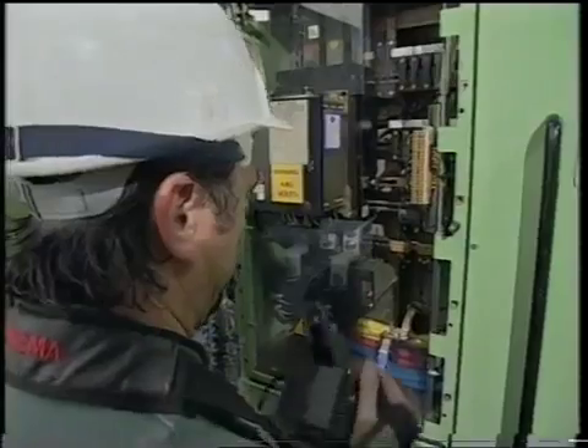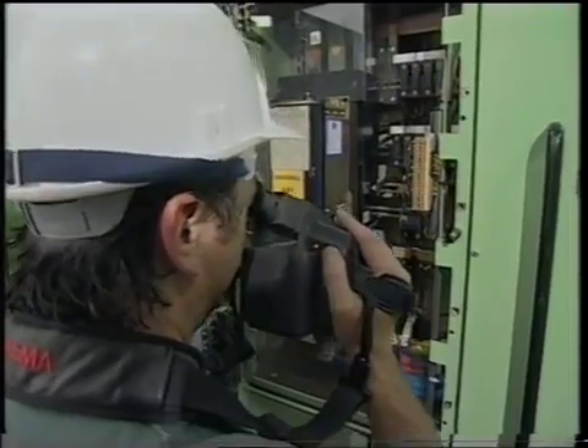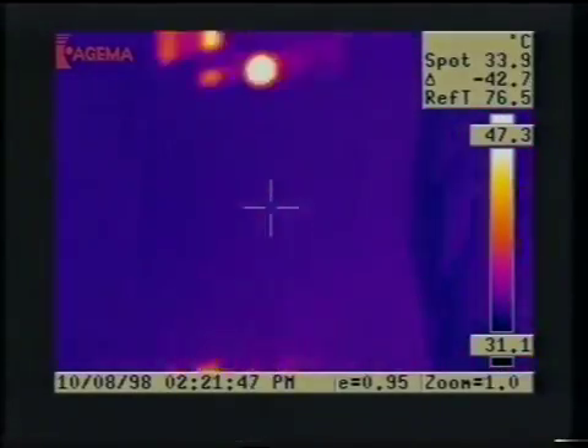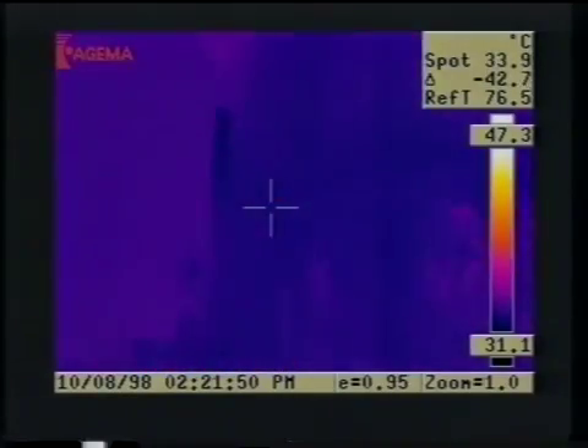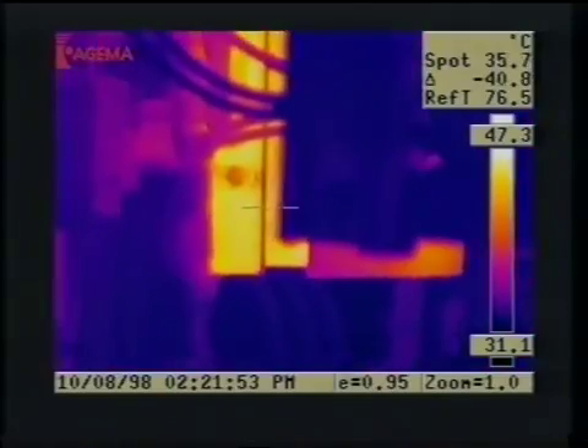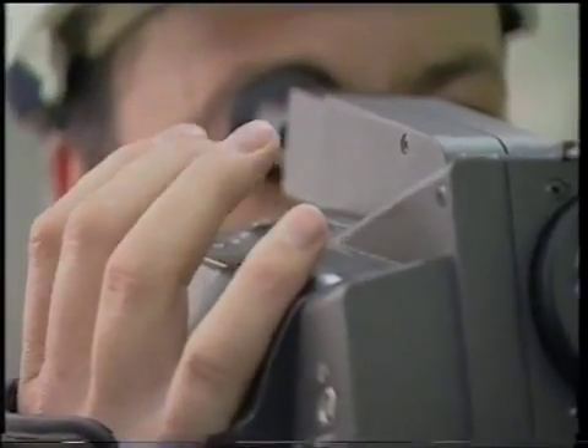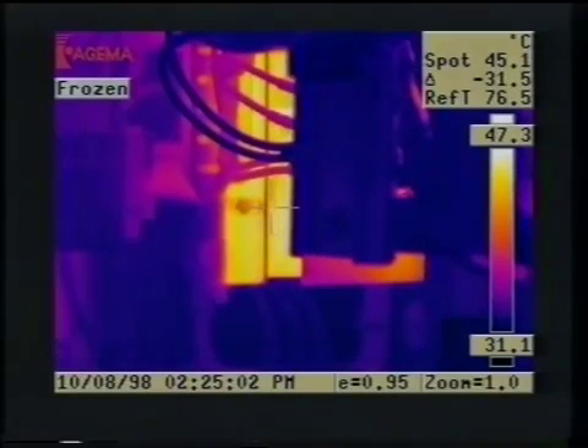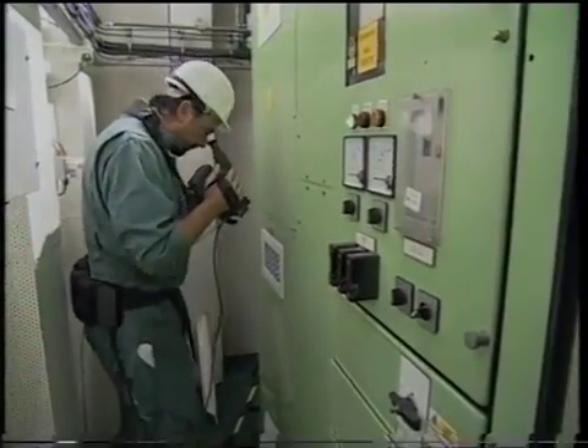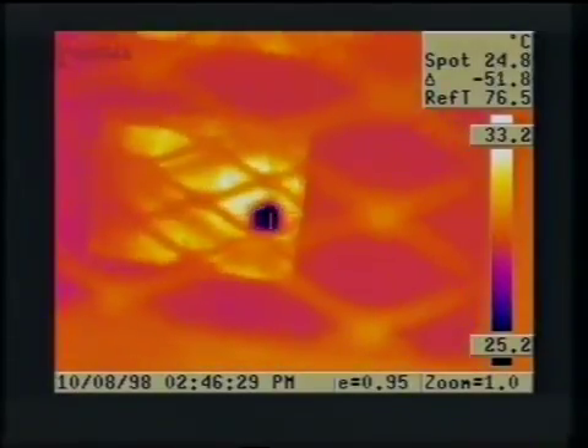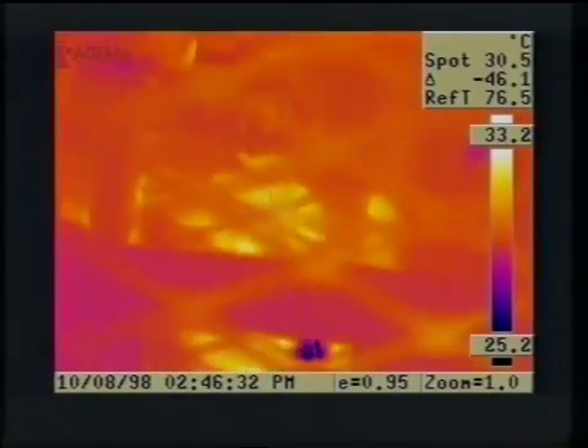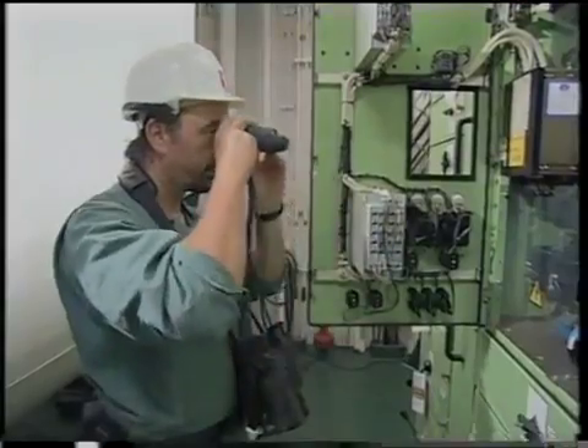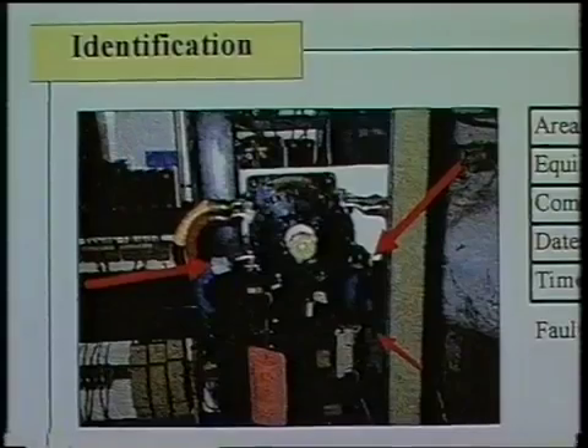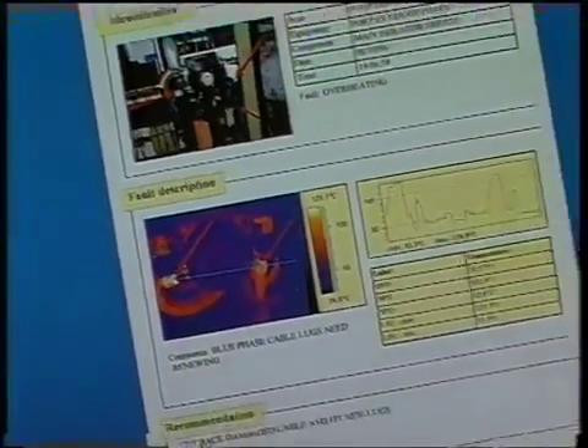Another periodic task is to check for local hotspots, and here the use of a special thermal imaging camera tells the operator where heat is being produced, for instance at a high resistance bus bar joint. The camera can freeze the image, and these still pictures can be downloaded to PC. A recent development is the introduction of special observation ports at the back of the high voltage cabinet to allow thermal observation without compromising safety. A digital stills camera provides a standard visual reference, and both kinds of image are incorporated in the contractor's report.